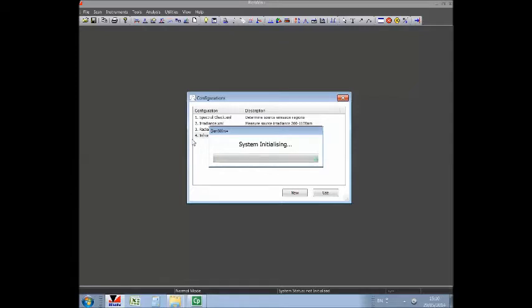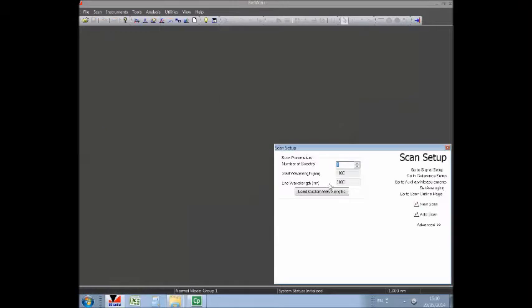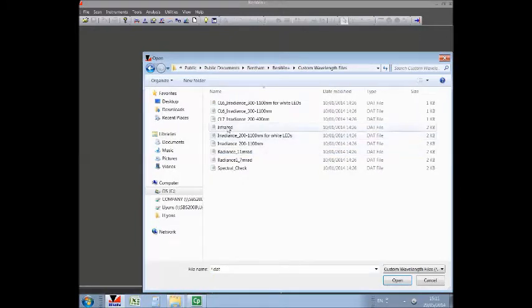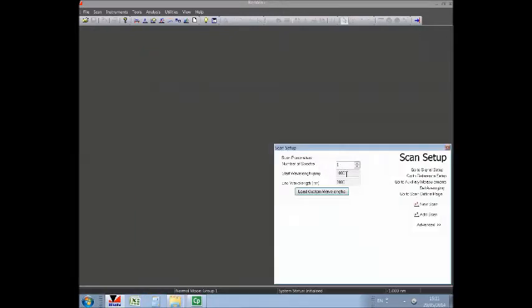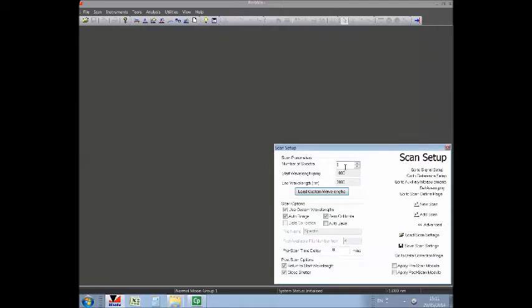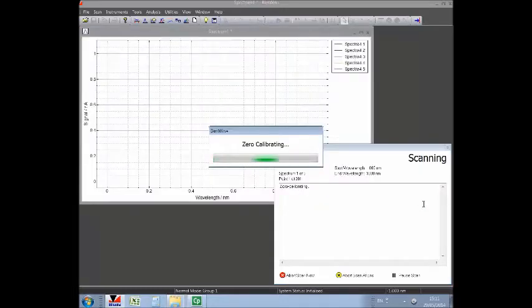Now the system is nearly finished, and we can go to scan setup. We have custom wavelength files, in keeping with the remainder of the system. Infrared is stepping from 1000 to 3000 nanometers in 10 nanometer steps. Let's do 5 scans for the moment with no data correction, and we will let that do the 0 calibration and the 5 scans. We will pick that up again in a short time.